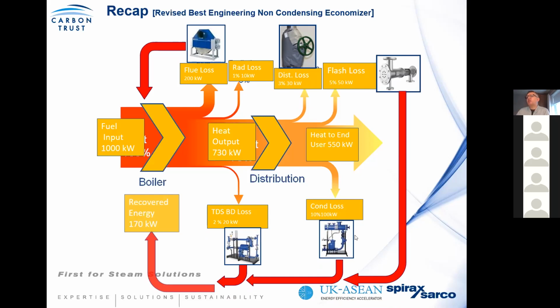Then start recovering all this energy, and you can see that very quickly you can start recovering a lot of the losses which are common faults in the steam system. So instead of having, like in this case, 1,000 kilowatts input, you could find that your fuel input could reduce quite significantly, making the system more efficient.